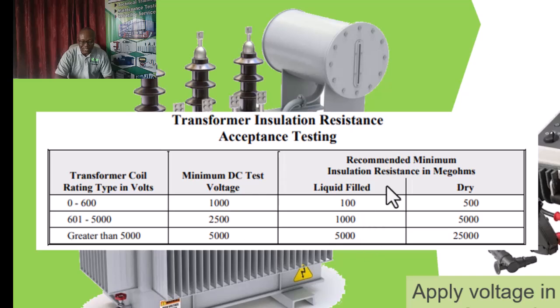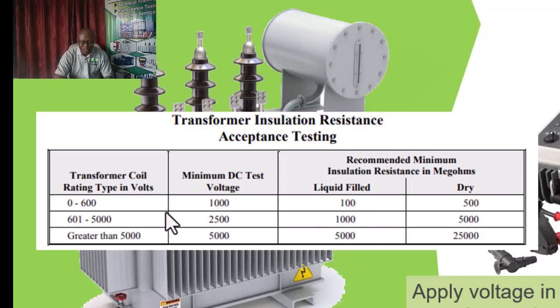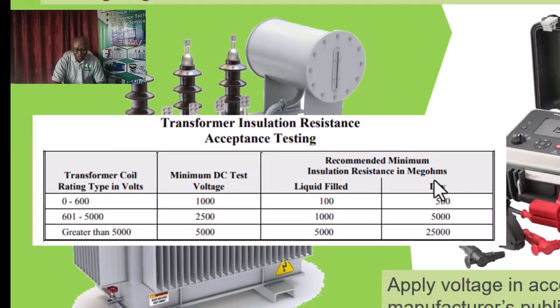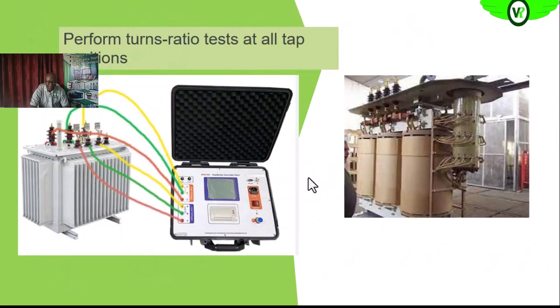So here are the recommended acceptable insulation resistances. Anything less than this will call for more investigation. For liquid filled transformers, low voltage transformers, 100 megaohms. For up to 5 kV, 1000 megaohms. More than that, we need to be more than 5000 megaohms. Therefore, for dry type transformers, this is the acceptable insulation level that we should be looking out for. Anything below that is cause for further investigation. We will also perform the turn ratio test. This one will give us an idea of the transformation ratio of the transformer.